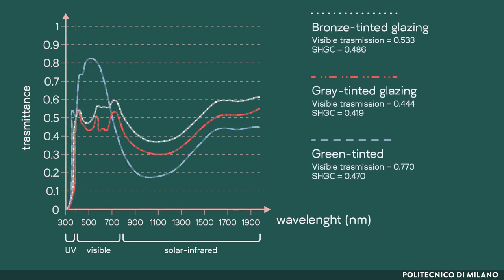Tinted glass changes the solar spectrum. If the glass is bronze or grey, light quality is little altered, but the low light transmittance leads to an increase in window surface, which outweighs the benefit of a low SHGC. In order to reduce the problem of high solar gains in buildings, spectrally selective glass, which can attenuate the infrared component of the solar spectrum while maintaining good transparency to visible radiation, can be adopted.